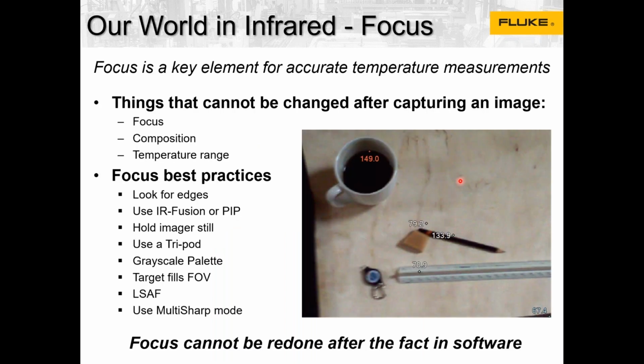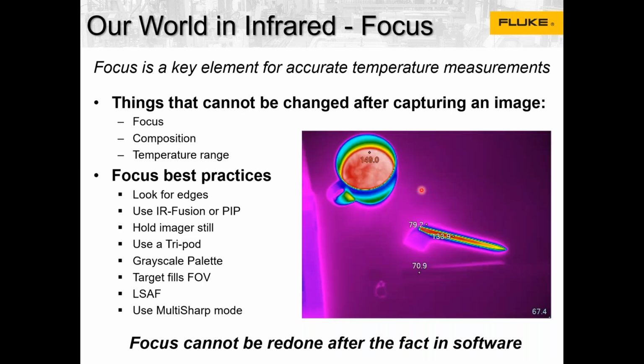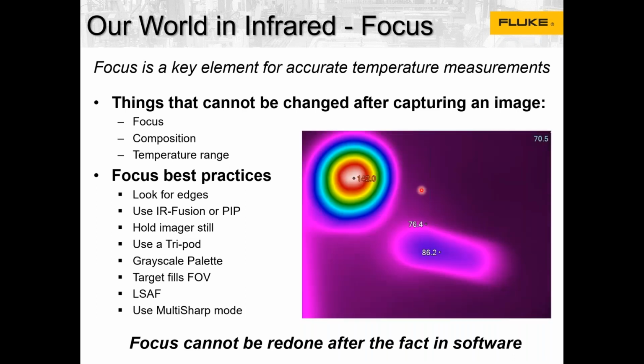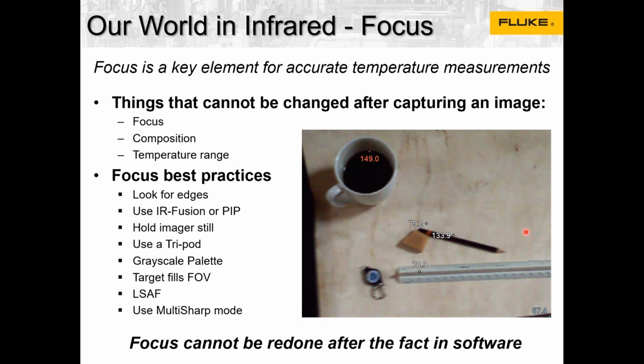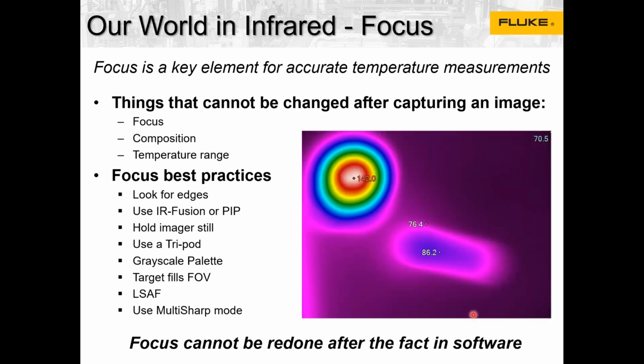So why is focus very important? You can see on this picture, for example, we have temperatures of 149 degrees and 133 degrees. This is a perfect focus. And you can imagine if we have a bad focus, we'll have a wrong temperature. So focus is very important. You need to have a perfect focus, because the focus cannot be redone after the fact in the software. You can change so many things except the focus: composition and the temperature range on the software. You can change the picture-in-picture. You can add a different palette. You can change the emissivity, but the focus you cannot change. So taking a better, focused picture will allow you to make a better analysis.